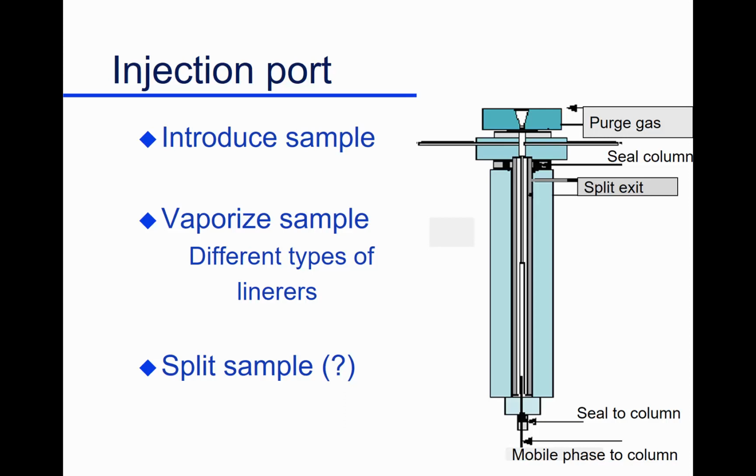We have several different ways of putting your sample into the system. I should have talked about initially a very, very simple one. This is our injection port. Here's our mobile phase coming in, so hydrogen or helium. This is a rubber septum, or a silicone rubber septum up here. So our gas comes in here, a little bit goes out here, and I'll explain why.